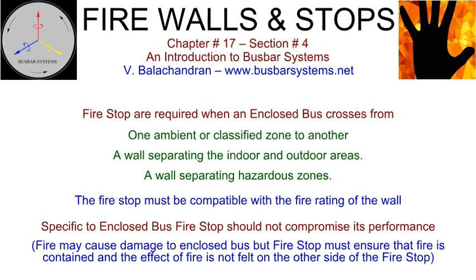Specific to an enclosed bus, it has to perform the following functions. Prevent the spread of flame or smoke, as per the specific requirements. Ensure that the performance of an enclosed bus is not compromised by the introduction of the fire stop. It is understood that in the event of a fire in one of the areas, the enclosed bus may get damaged beyond recognition along with the fire stop, but it must ensure that the effect of fire is not felt on the other side of the fire stop.